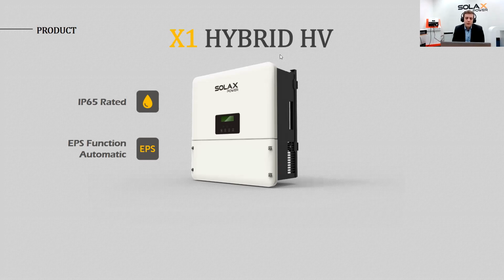So that means with the X1 hybrid, you can have a system from a 3 kilowatt battery up to, I'd say, 20 kilowatts. I don't know if it really makes sense to connect a 25 kilowatt battery to a 5 kilowatt inverter, but the possibility is there. So basically you can go from a 3 kilowatt battery up to 25 with one inverter, and if you use the master-slave option with the X3 inverters, you can even go up to 250 kilowatts of battery capacity.